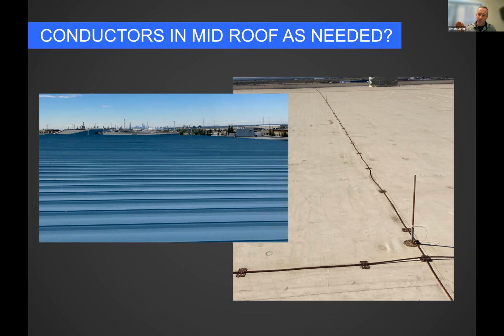And for long roofs, really big roofs, if they exceed 45 meters on any given run for that mid-roof conductor, we need to interconnect that again in the opposite direction. So any grid on a roof is going to be 15 meters one way and 45 meters average spacing the other way, no more than 45 meters spacing.